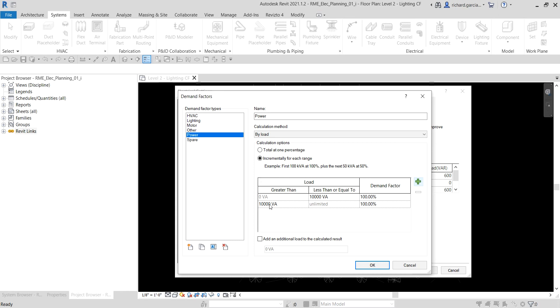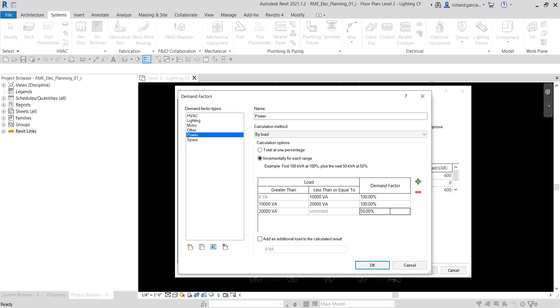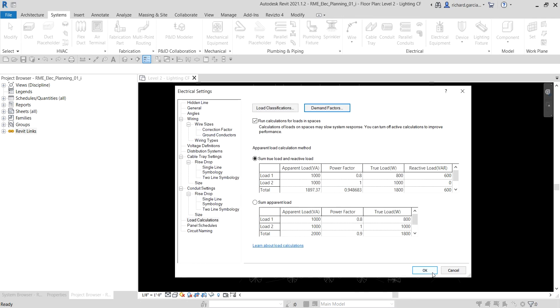I'll add a split at 10,000 volt-amperes, then split again to create a range for greater than 10,000 up to 20,000 volt-amperes with a demand factor of 100%. For the range greater than 20,000 volt-amperes up to unlimited, I'll set the demand factor to 50%. That's how you modify the electrical settings for your electrical design. Click OK to confirm.